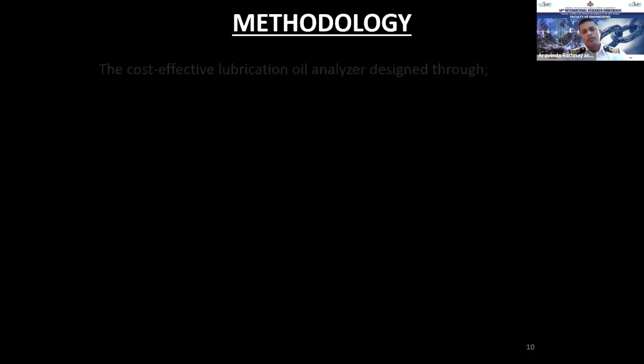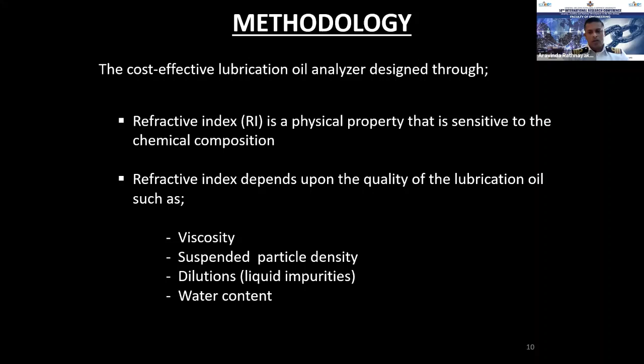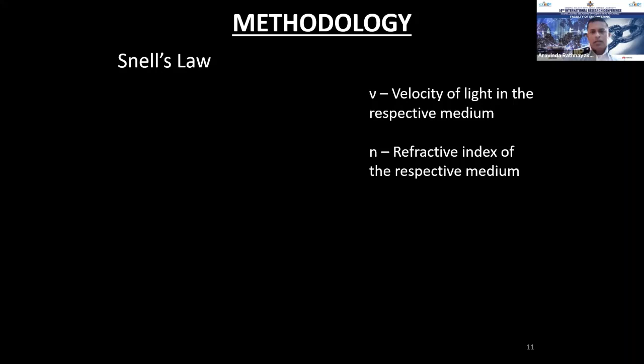As I told you, because of that method, I have selected the refractive index to analyze the lubrication oil. The refractive index depends upon the quality of the lubrication oil, such as its viscosity, suspended particle density, and also water content. The deviation of a light beam depends upon the velocity of the light in a medium, and also the refractive index of that medium.